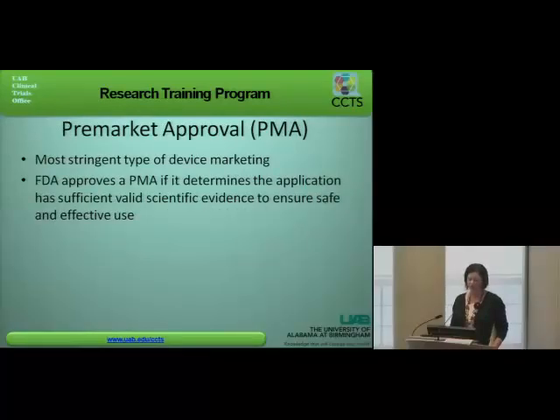The second process for a device to get to market is a pre-market approval process, or the PMA process. Typically, Class 3 devices must go this route. It's the most stringent type of device marketing, and if the FDA approves a PMA, it has determined the application has sufficient valid scientific evidence to ensure safe and effective use. Interestingly enough, only 10% of devices are considered by the FDA to be Class 3, which means only about 10% of devices go through this PMA process.